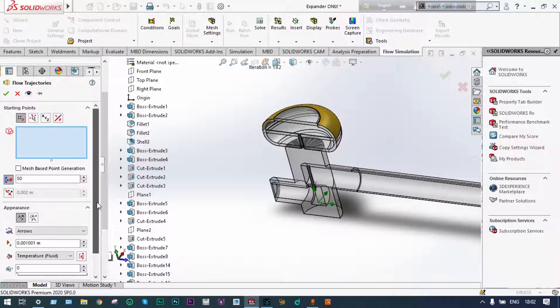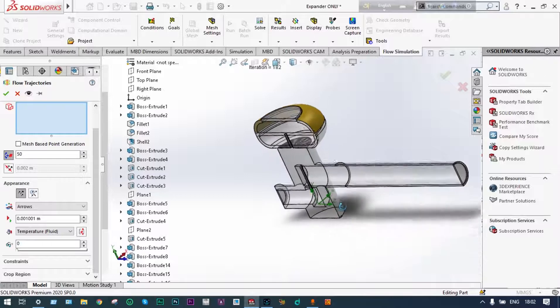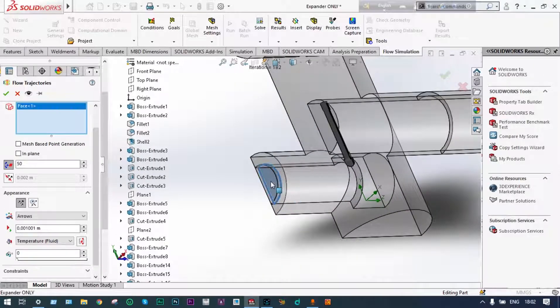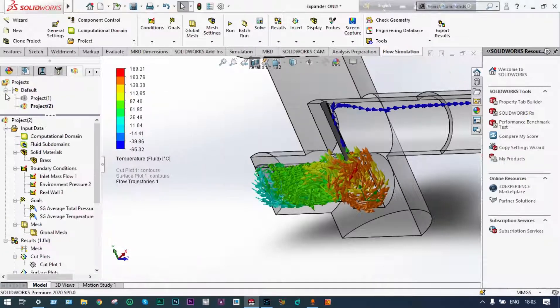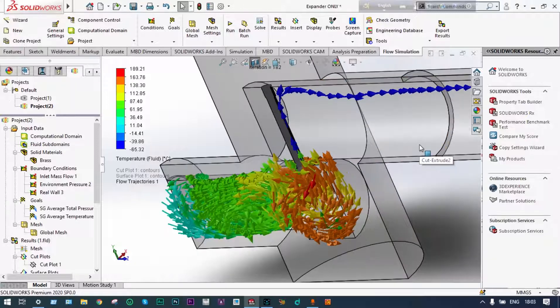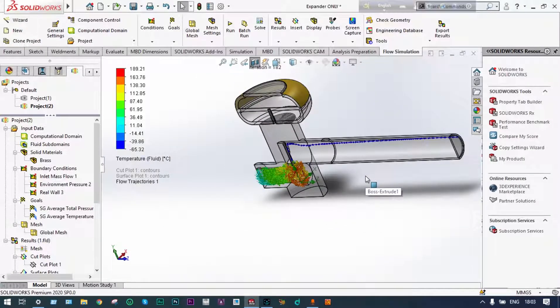We want to see temperature of the fluid from left-hand side to right-hand side, so we select that location. Face one is selected. You can see the particles moving — some kind of circular motion is created inside, and after passing through the small opening it maintains a streamlined motion of Freon particles at a very low temperature of minus 65 degrees centigrade.